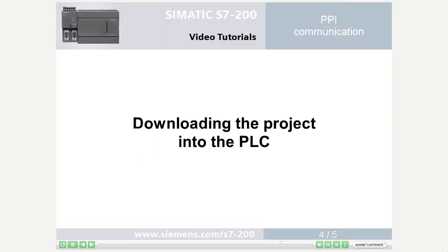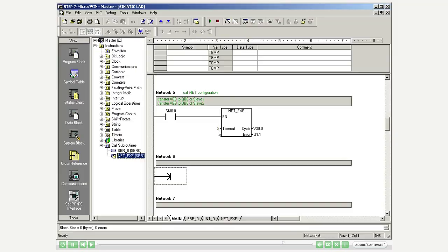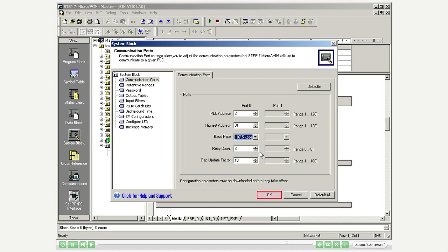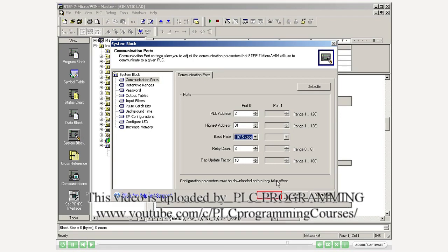Step 4: downloading the project into the PLC. Open the system block and select PLC address 2 for the master, and set the same baud rate as for the slaves. Then you download the project to the master PLC.